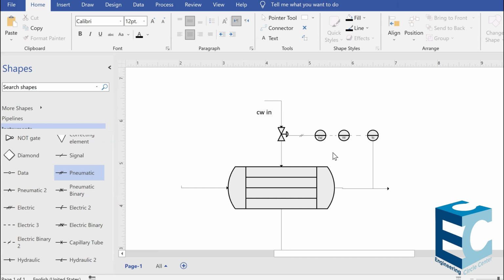So if the temperature leaving here is not as cold as I want it to be, what happens? The controller will order the valve to increase its opening and let in more cooling water, increasing the flow rate of cooling water entering the shell side of the heat exchanger. This way, the temperature of the process fluid leaving will be lower, closer to the design temperature required.